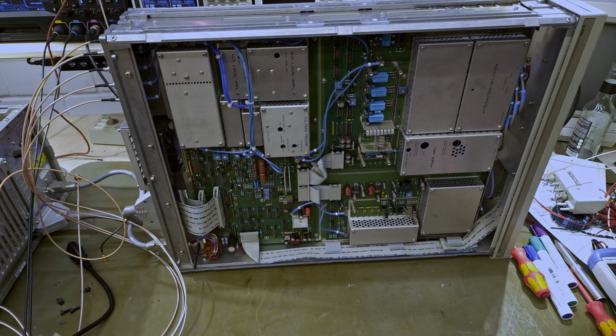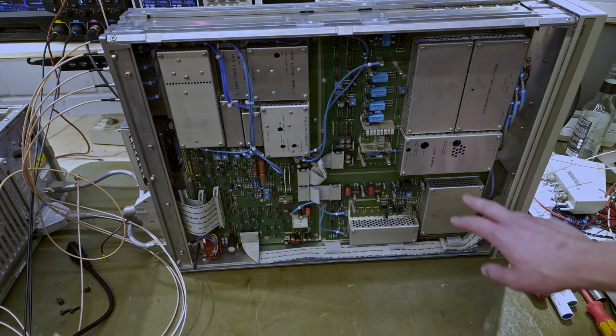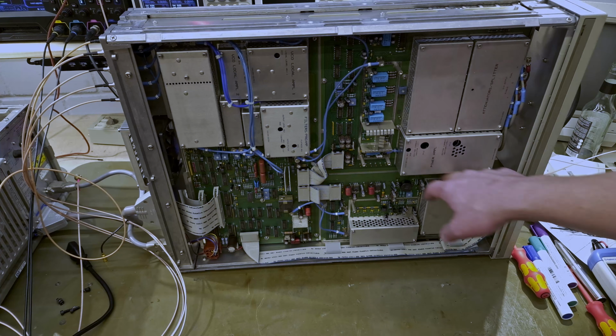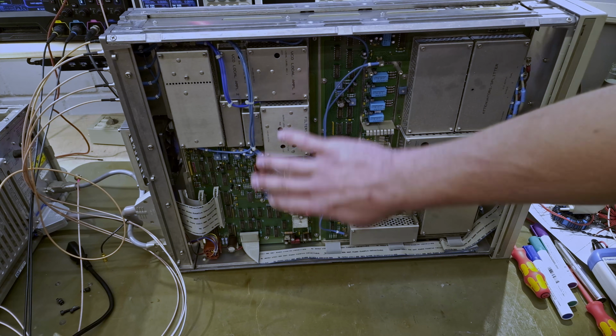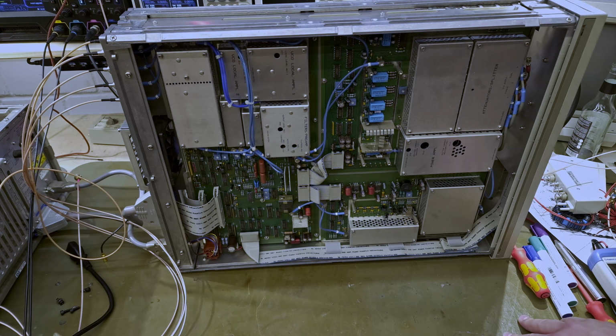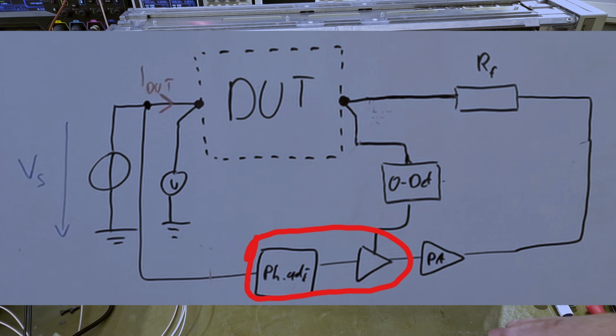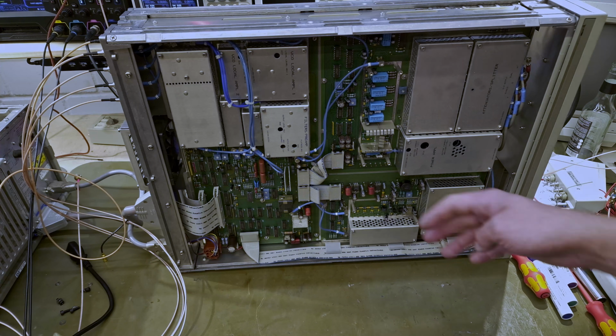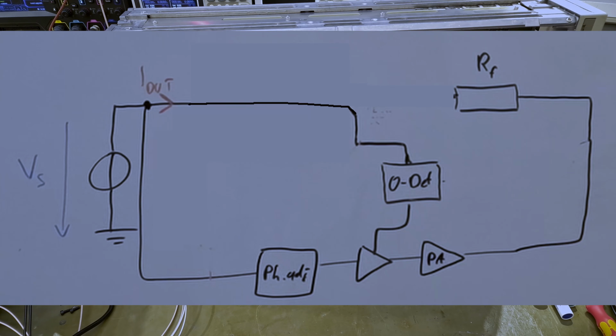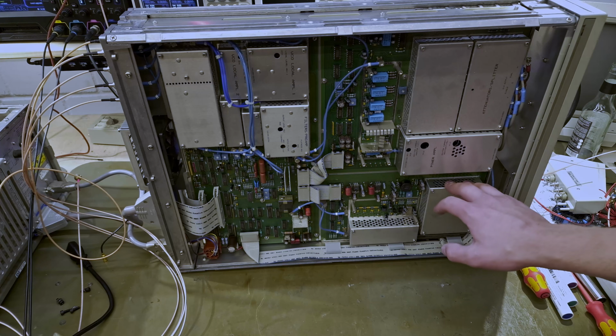So how did I actually diagnose it? Well, there are a few steps in the service manual that allow you to check the null detector as well as the feedback oscillator, you might call it, I'm not sure. This one. And basically what they do is they tell you to connect the output of the high side to the feedback of the low side, not the current input, but the actual measurement input. And then look at some signals.